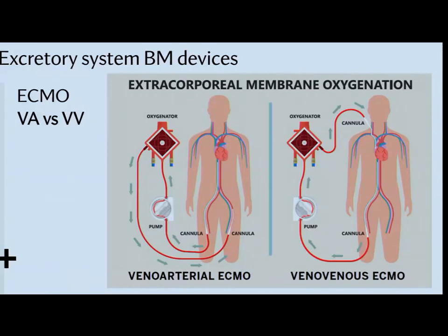So the other challenge with this is the priming. If this circuitry is air-filled and the blood enters, all that air is going to be bubbles going back in the bloodstream. So you actually want to prime it with the full volume to fill those up. So that's why they take a large sample from the patient's blood right before to fill the circuitry, and then they actually use the circulation to go forward.